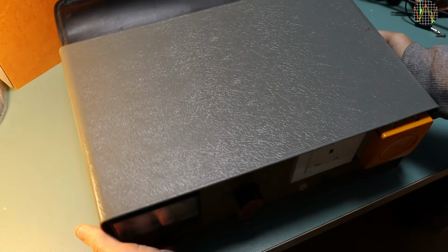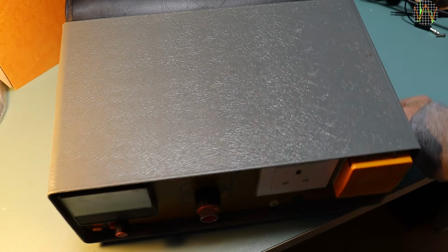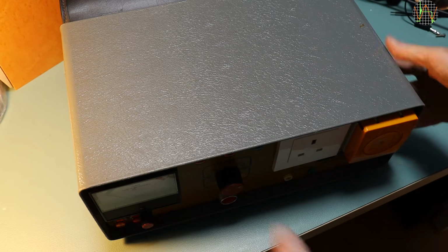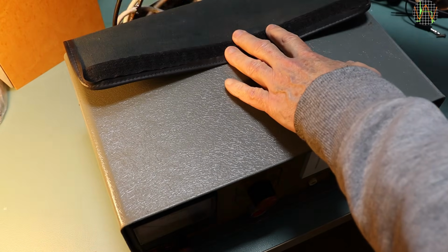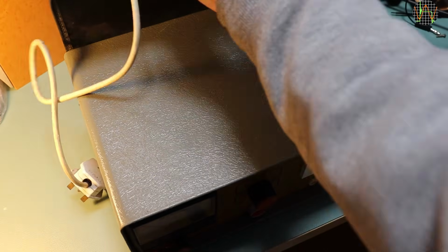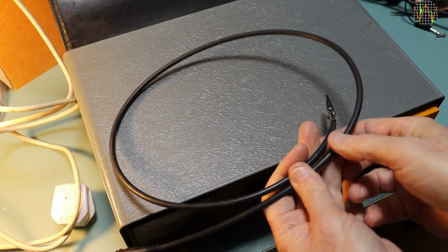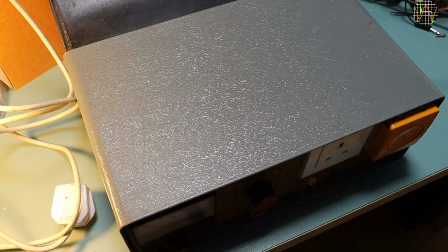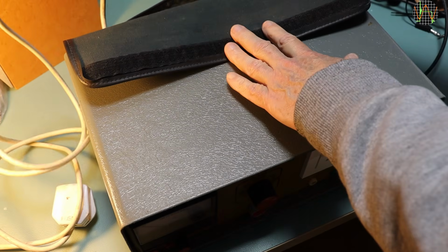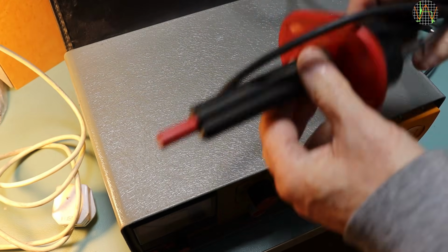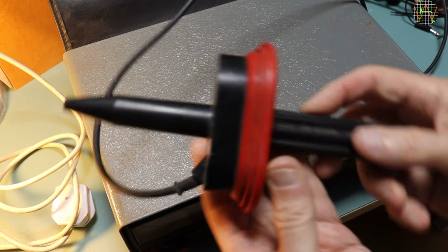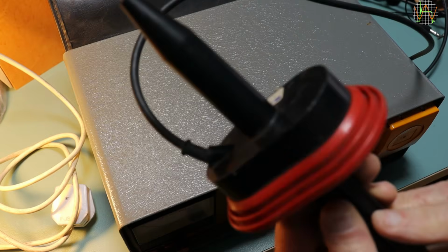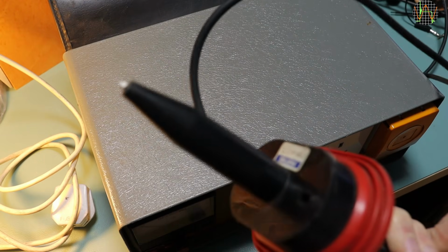This unit is supposed to be transportable to sites. It has a carry handle on one side and a leather pouch on the back for cables and such. In my case, it contains the power cord, which is fixed to the unit, a black wire for earth bonding tests that I actually made myself. It wasn't part of the unit. It's 4 mm square and has a really low resistance, and a high voltage probe on a cable, again permanently fixed to the unit. For safety reasons, the probe has a plunger on the rear that needs to be pressed and kept down for the metal tip to come out.